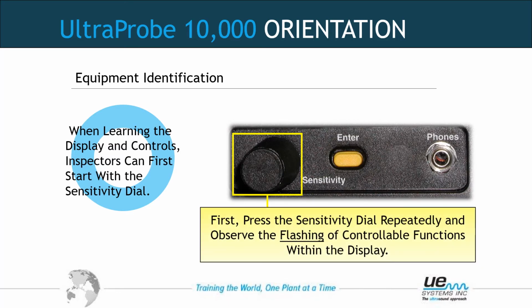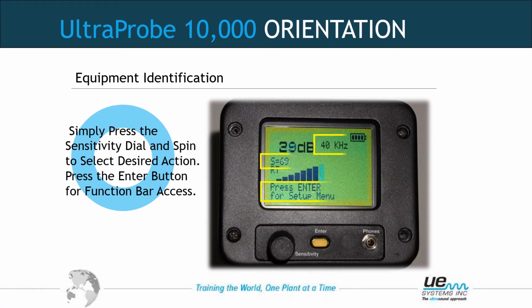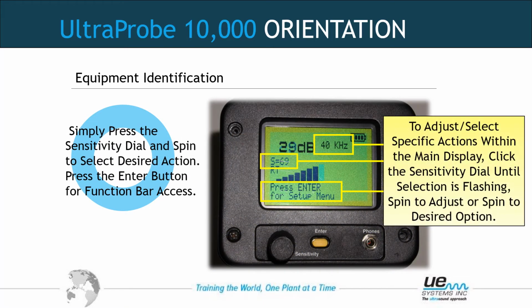So when learning the displays and controls, inspectors can first start with the sensitivity dial. First, press the sensitivity dial repeatedly, slowly, and observe the flashing of the controllable functions within the display. These are the 3 cursor areas that we can adjust on the main display by pressing the sensitivity button. Your home resting spot would be sensitivity. When S equals is flashing, you can adjust your sensitivity.